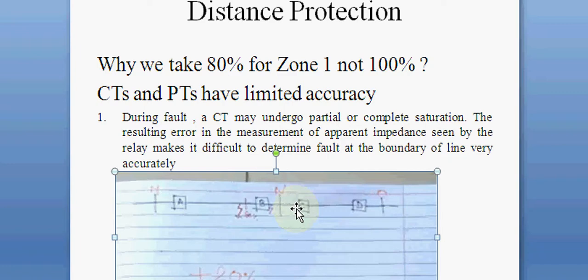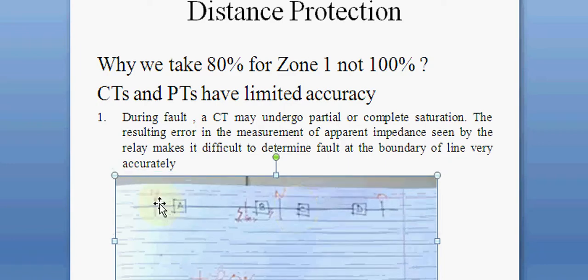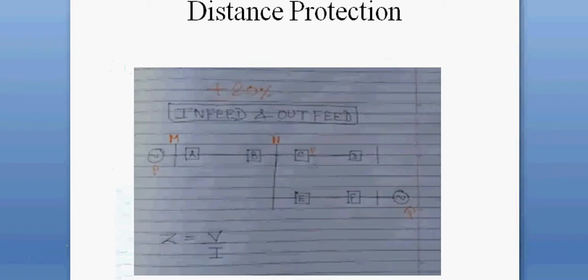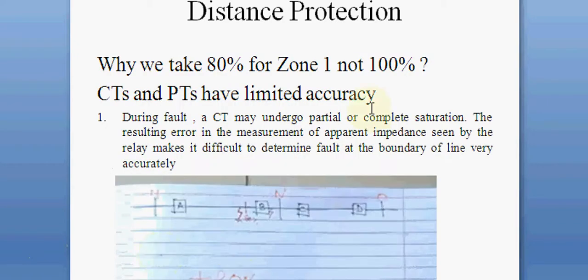Another reason for keeping Zone 1 at 80% is that when deriving the torque equation or the mathematical equation for the relay, we do not compensate for the effect of capacitance or transposition of the line. These effects will affect the measurement in practice, so we keep Zone 1 only up to 80% of the line.